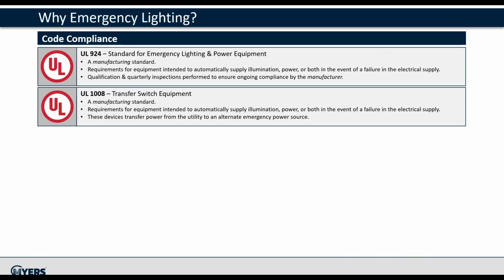Anytime you're discussing emergency lighting, it always starts with the codes. A whole seminar can be dedicated to emergency lighting rules and regulations, but I will highlight some of the major codes from manufacturing to maintenance. The first two, UL 924 and UL 1008, are manufacturing standards that are in place to ensure the equipment will automatically supply the intended illumination in the event of a failure with the electrical supply. UL 924 regulations mainly cover the backup power source, and UL 1008 regulations govern transfer switches and equipment that typically transfers power from a normal power source and emergency power source.